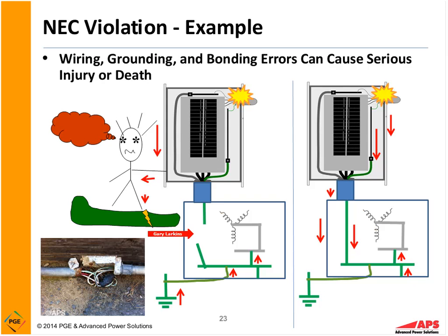So up here in the upper side of that panel, we see there's a fault, let's say a phase to ground fault. The fault current is supposed to flow back up to the source. You can see the arrows there, flow back up to the source through this wire, but the wire isn't there anymore. It's been broken or it's loose. So now the whole equipment could be energized, and whoever comes up and touches that cabinet can receive electrical shock or, worse yet, be electrocuted.